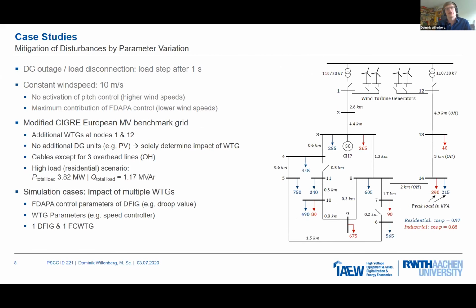To identify if it's possible to mitigate disturbances by parameter variation, a modified CIGRE European MV benchmark grid is set up, where we have additional wind turbine generators at nodes 1 and 12, and no additional DG units. This is done to solely determine the impact of the WTG generators. A high load scenario is chosen.